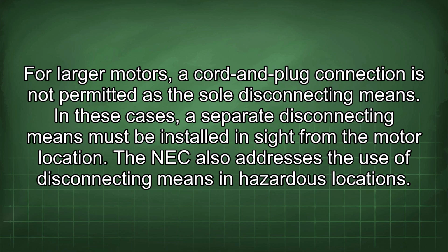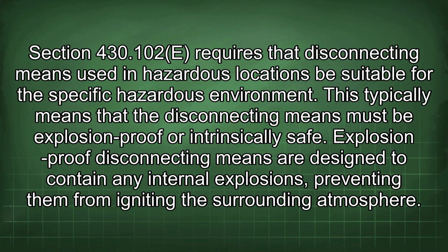In these cases, a separate disconnecting means must be installed in sight from the motor location. The NEC also addresses the use of disconnecting means in hazardous locations. Section 430.102E requires that disconnecting means used in hazardous locations be suitable for the specific hazardous environment.